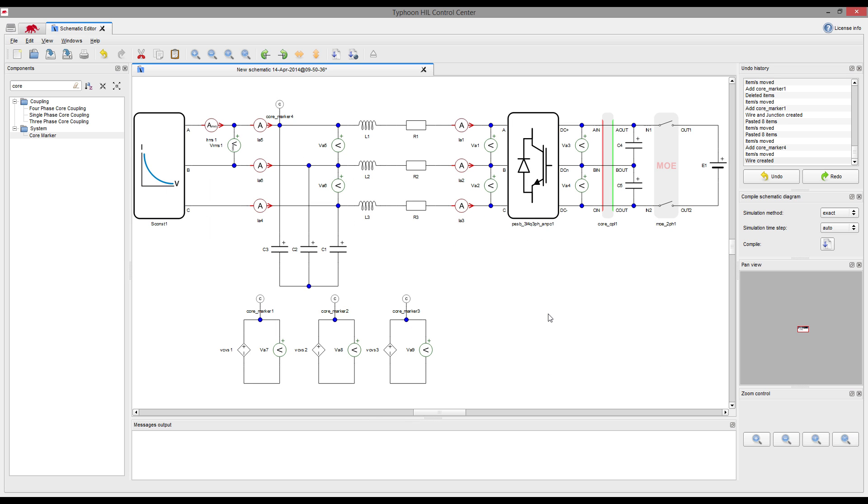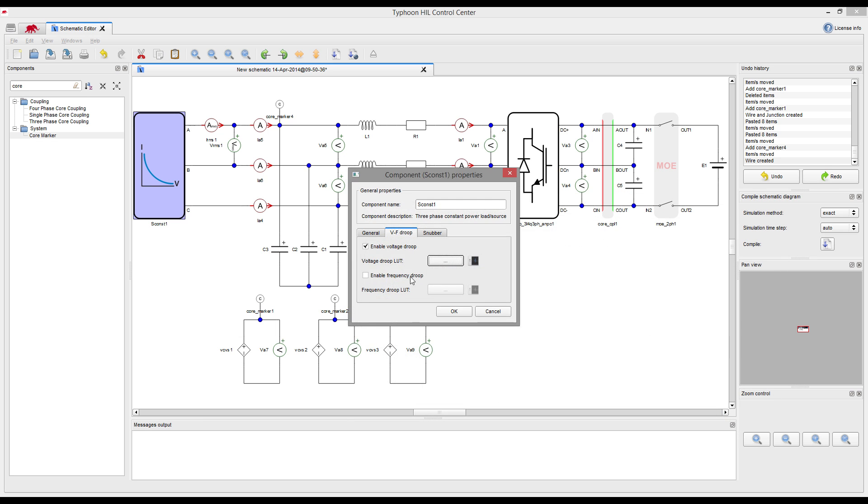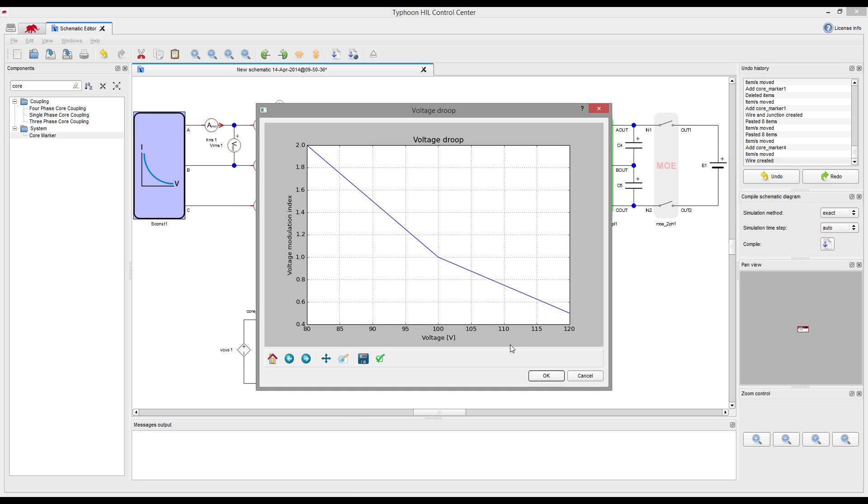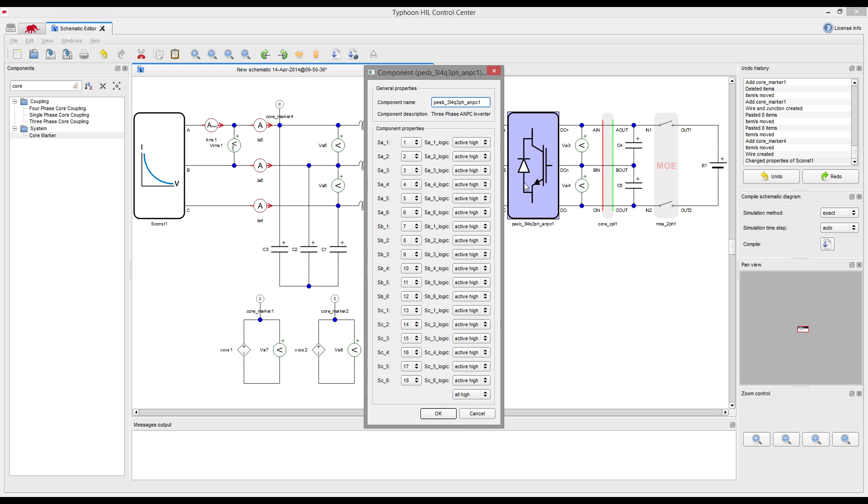Before compiling, we need to set circuit-breaking digital inputs and power source parameters, such as current limit, frequency, and voltage droop characteristics. And also define which HIL digital inputs we want to use to control our ANPC switching block.